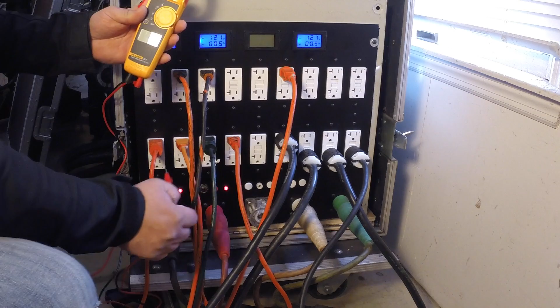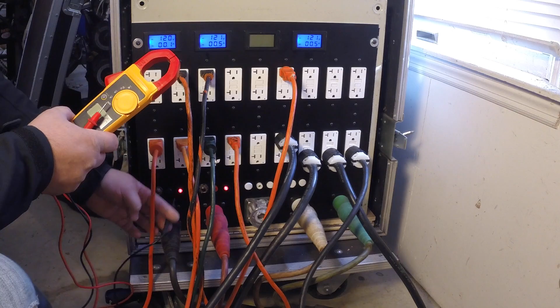242.5 volts AC. So if I put it across one of the hots and the neutral, it shows me half of that, or roughly half. So these probe points are kind of like a safety feature, so you don't have to actually go into the back of the panel and put your test probe right on something hot.